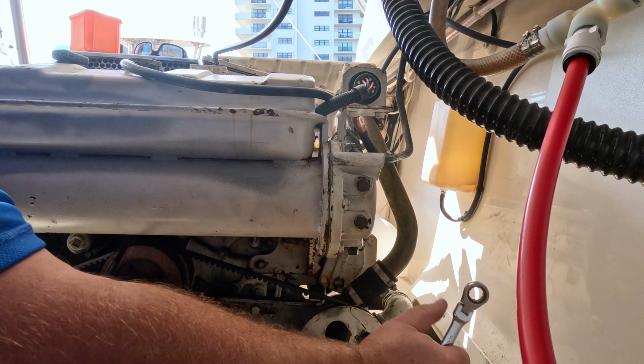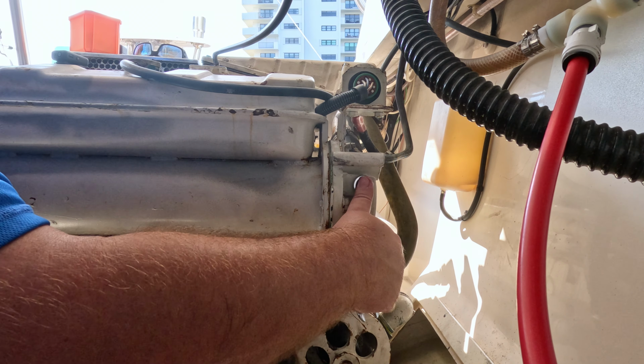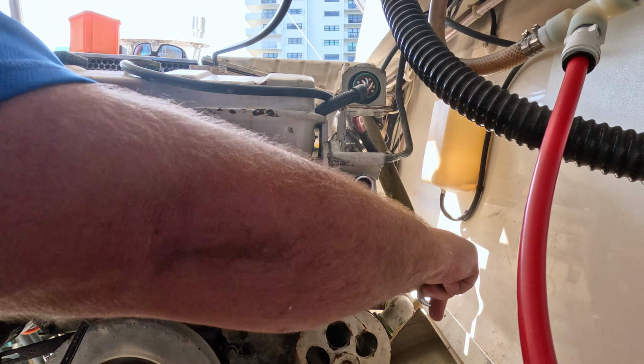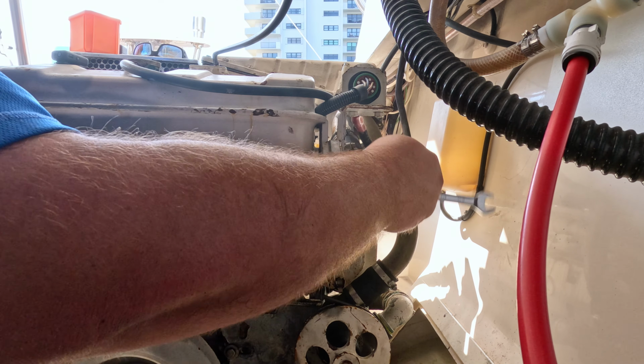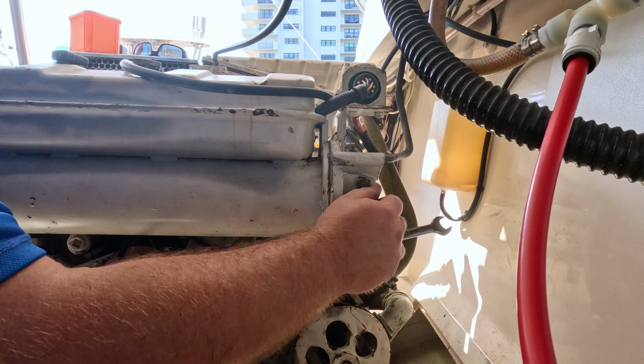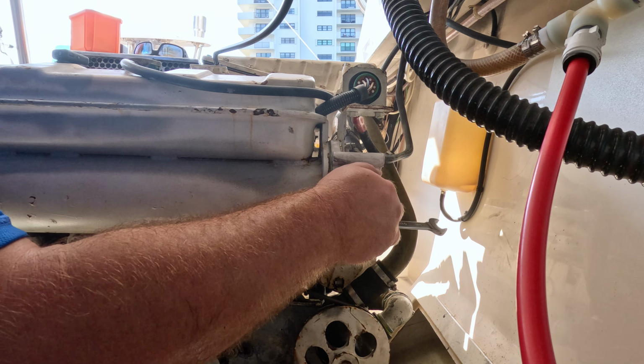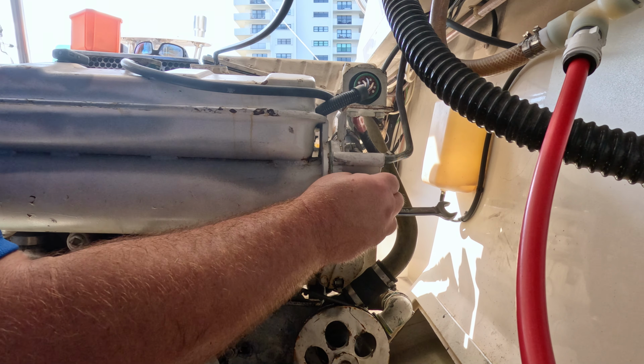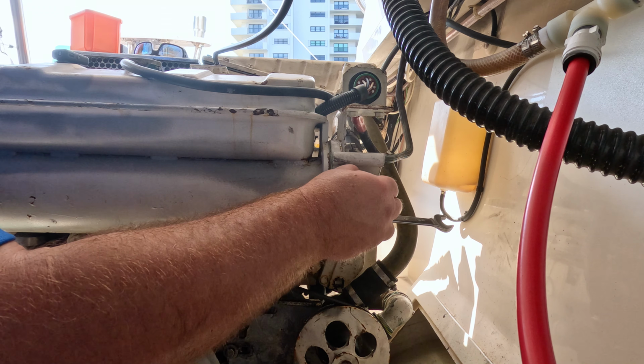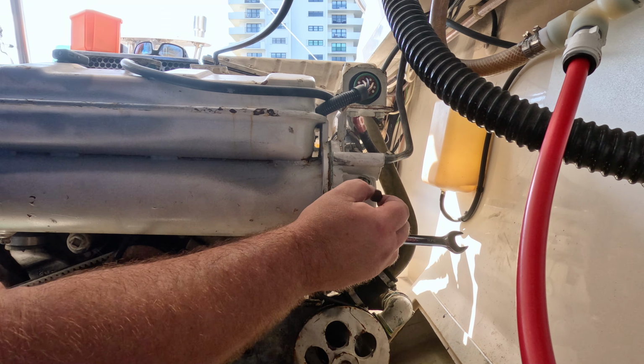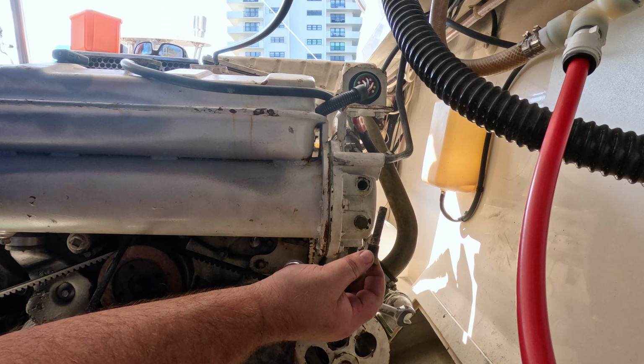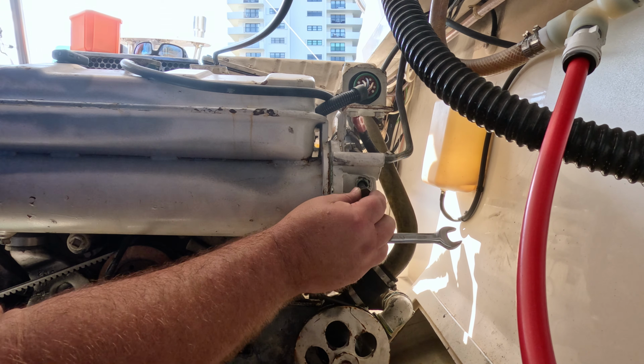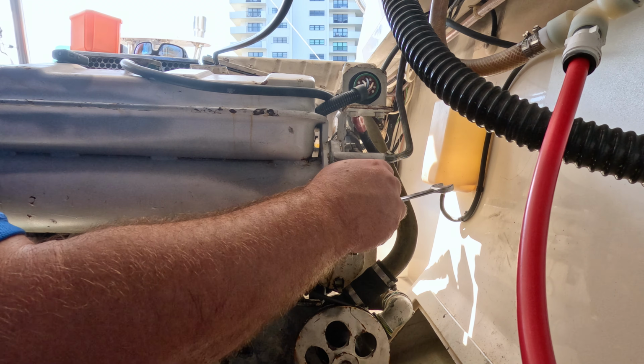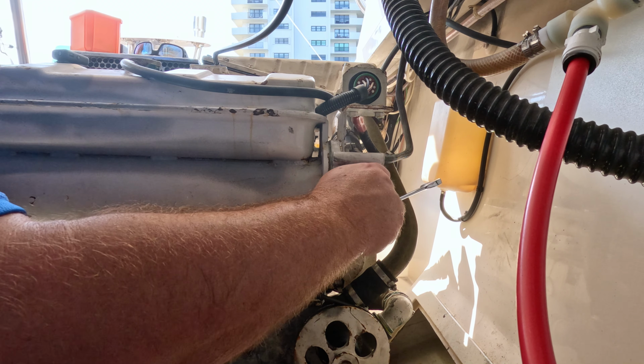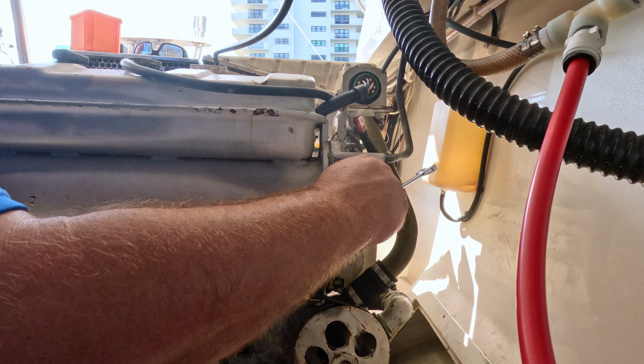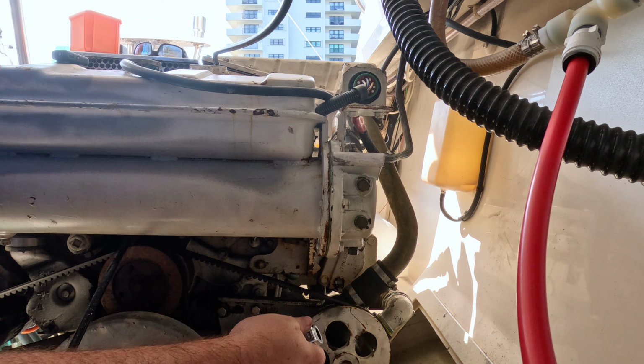Then I'm going to check this other one. So on the heat exchanger on the 3208, you have 3 zincs - there's 2 on this side, which is on the water pump side. The water comes in and then goes to the aftercooler, and from the aftercooler it comes down to the heat exchanger, so I want to make sure I check both sides. This one feels not too bad, so it's actually about the same. Those have both been, looks like they've been done recently, so I'll log that so I know that they're still good, and I'll look at how much time has passed since the last time I changed them.